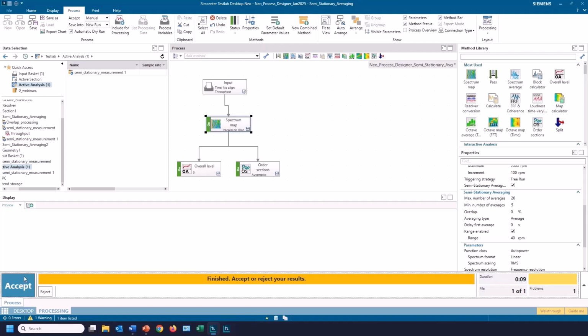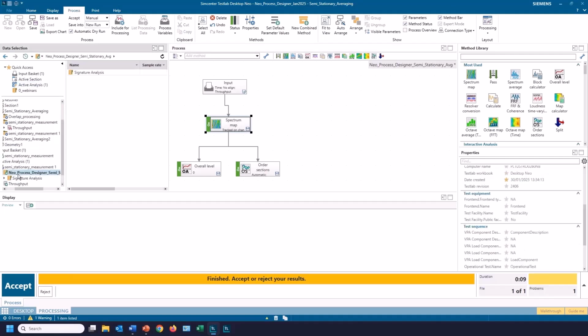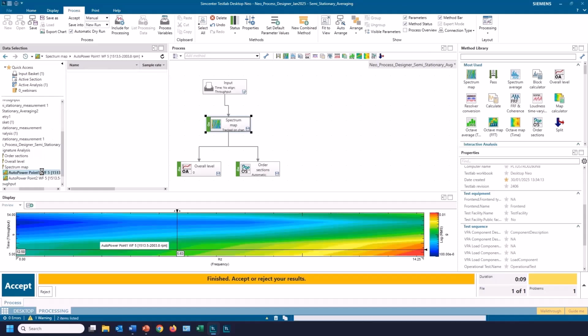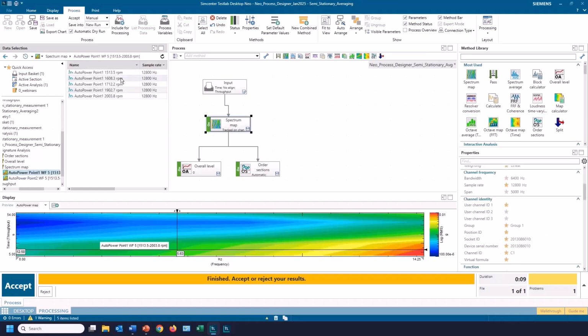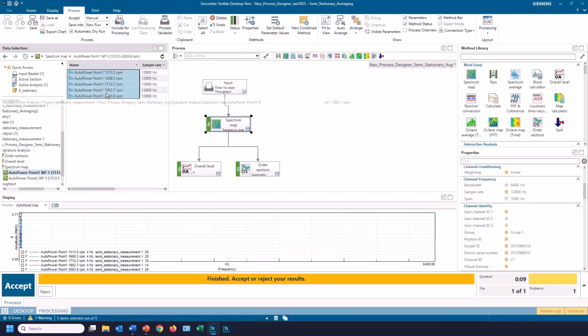And then some of the blocks will have less averages as well. So if I look at this and look at my waterfall blocks again, so there it has 5 blocks now instead of 6. So it skipped a block. So it skipped a block around 800 RPM because we didn't have 5 averages there, within plus or minus 20 RPM because I had a range of 40 specified.